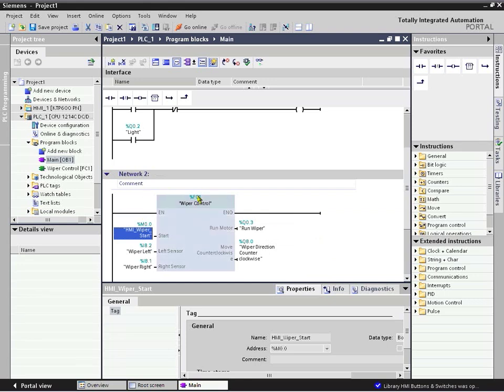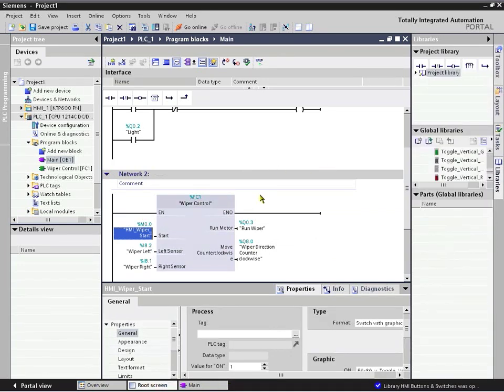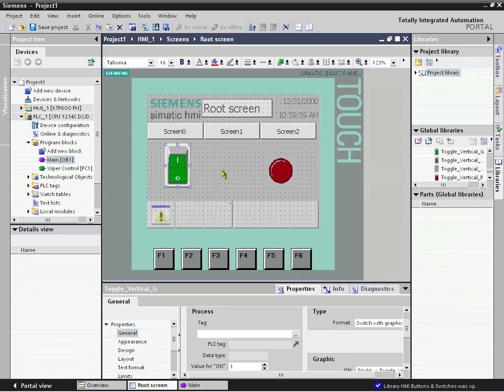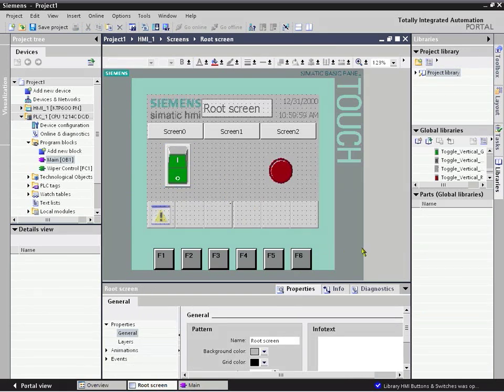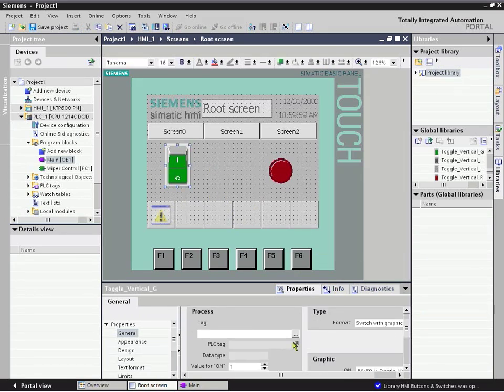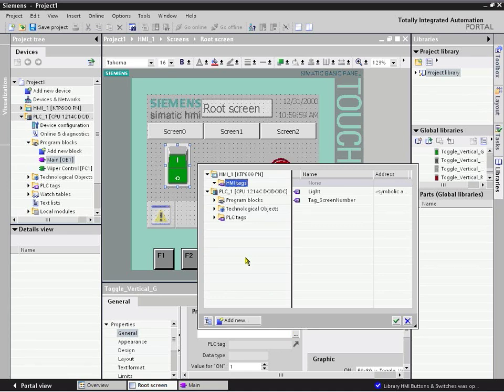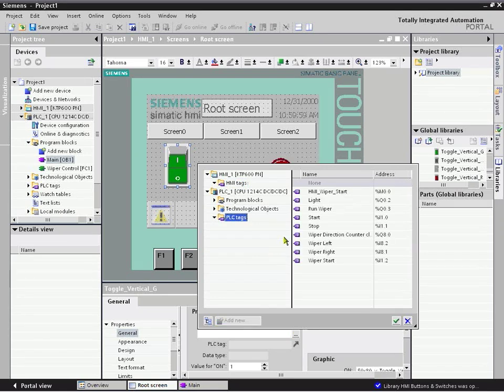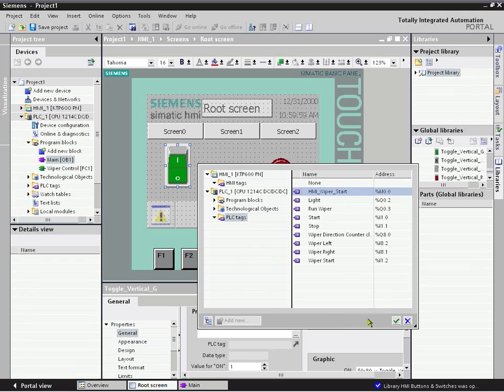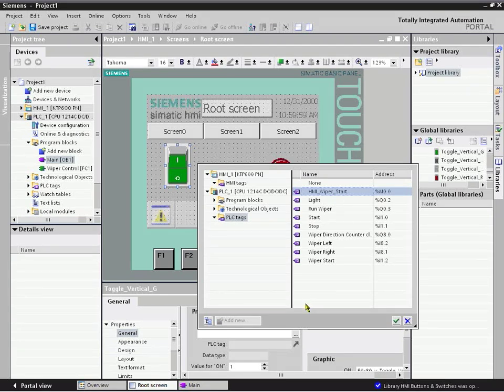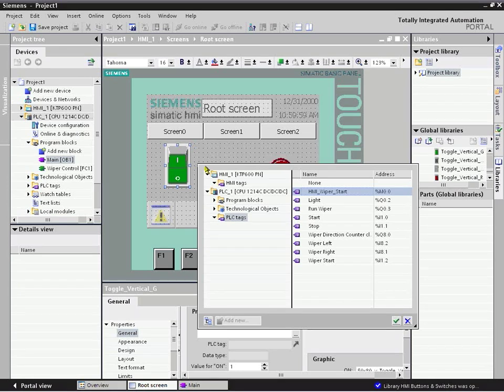Then similarly, we can go back to our screen, which is still available all in the same environment, and go to its tag field, and we can bring in the PLC tags. We can use that by using the three dots instead of drag and dropping. We've got preferences for navigation for many different methods. And there's our HMI start. Accept it, and now we have it linked within the programming environment.